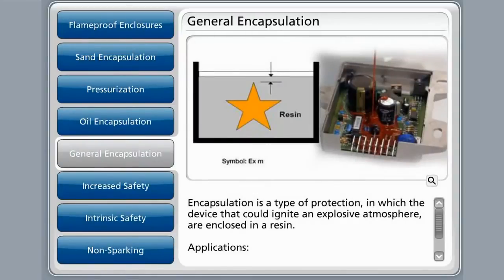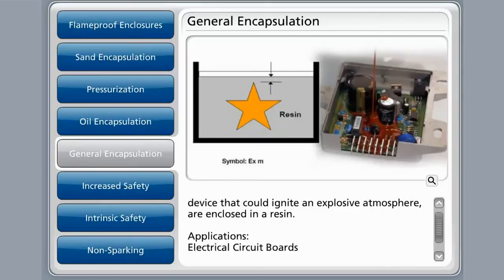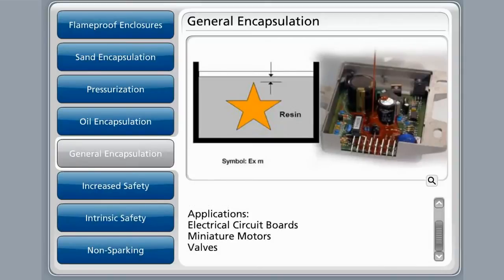Encapsulation is a type of protection in which devices that could ignite an explosive atmosphere are enclosed within a resin. The material used would be resistant to environmental influences, heat, and sparking from electrical components. The general application for this protective method would be used for electrical circuit boards, miniature motors, and valves.